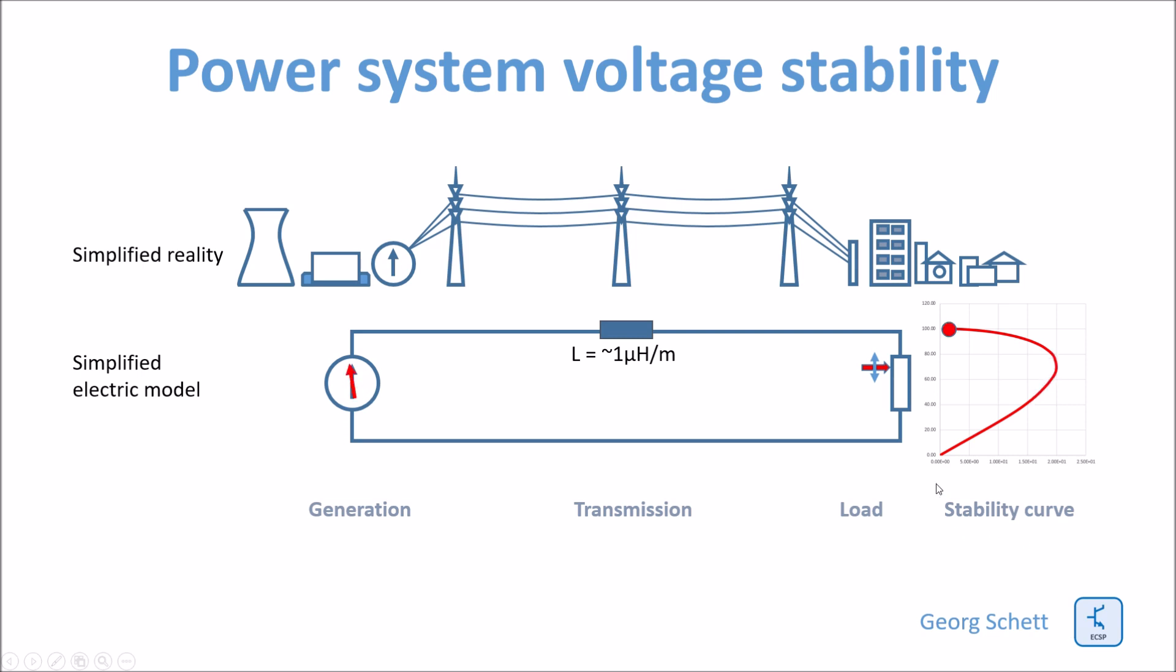What you would also observe is a phase angle shift between the voltage at the load and the voltage at the source. Above the tipping point, this phase angle would basically also collapse. So the generator would just be accelerated. It cannot evacuate the power anymore into the network. Therefore, the speed of the generator would accelerate.